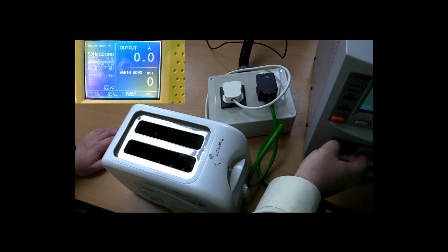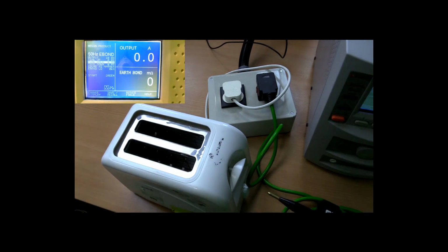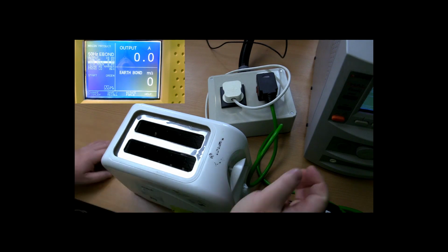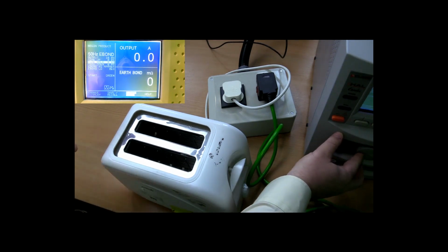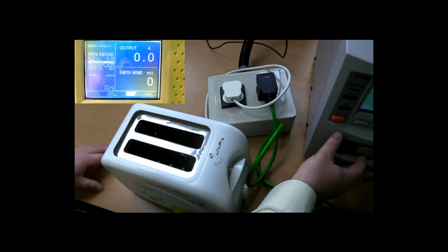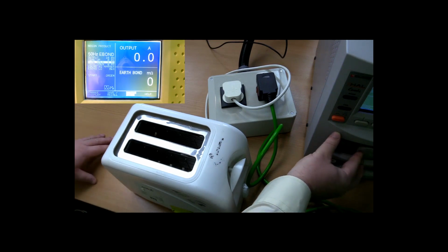Now, test time is configured as long as it's needed to take that measurement. So something like a second or two would be more than adequate for this particular test. This is for the production standard, so routine testing. So let's set that to 2 seconds.